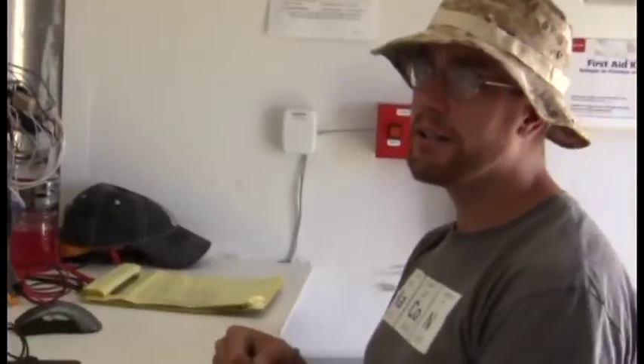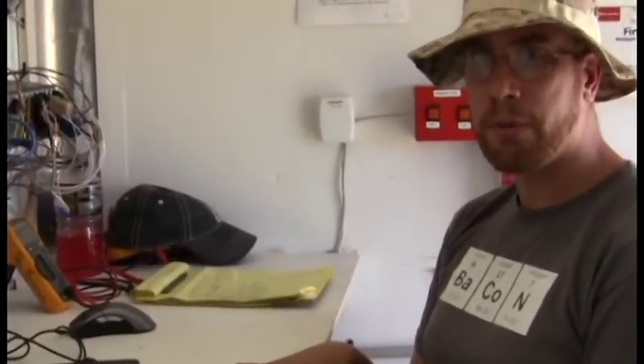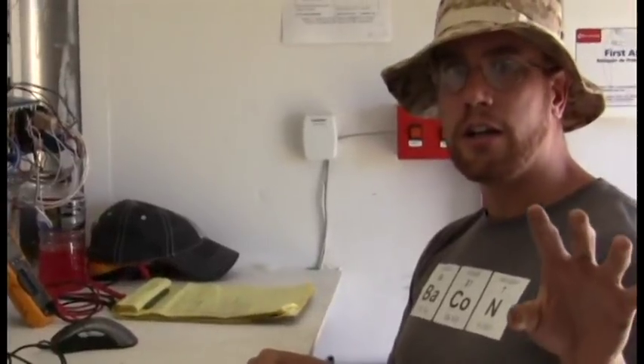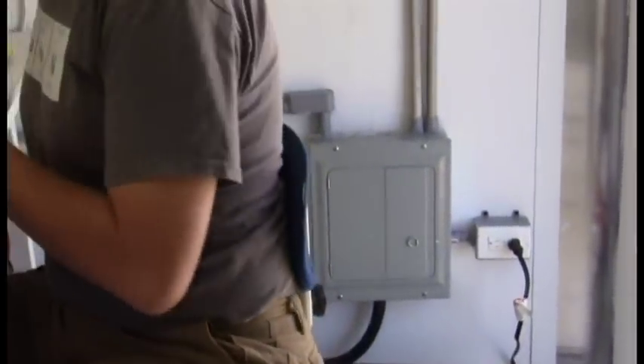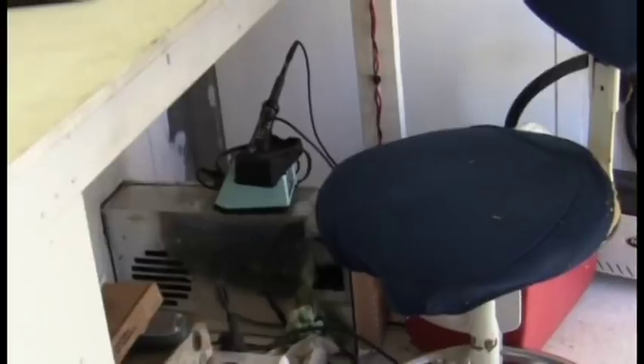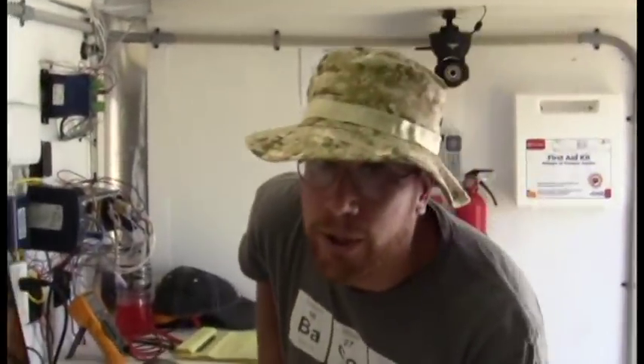The most important bit is the air conditioner behind you, to keep this metal box nice and cool. For the winter, we've got three different heaters on board. The primary is actually in the air conditioner — it's a heat pump, so the air conditioner runs in reverse in the wintertime, bringing all that warm air in here. In the event that it becomes too cold for that to work, there's also a 1700-watt heating element in that heater. If that can't keep up, we've got a radiant heater up front, and in the event that we lose power and still need heat, there's a propane-fired heater located underneath, with two 20-gallon propane bottles mounted up front on the tongue of the trailer in the wintertime.